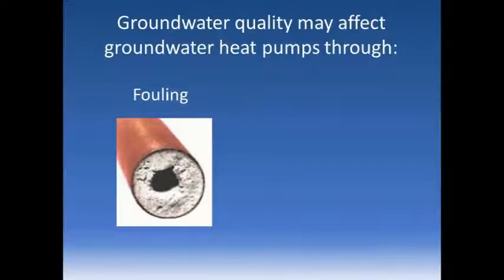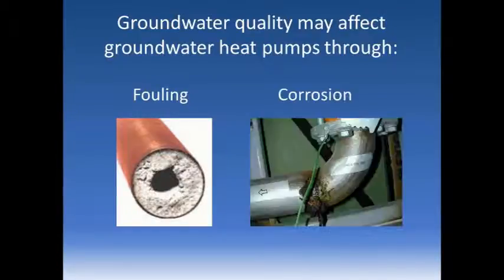Groundwater quality can affect heat pump operation through fouling, which is the depositing of precipitates on heat exchanger surfaces. This example isn't a heat exchanger, it's a domestic hot water line, but it shows that calcium carbonate deposition can sometimes be a problem. The other possible effect is corrosion, though I won't have too much to say about that—mostly I'll focus on fouling.